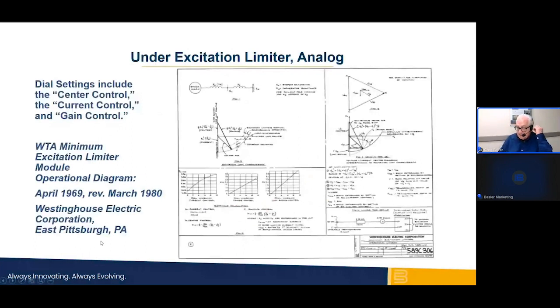The industry has relied on solid-state electronic analog control systems since they were invented. The underexcitation limiters and these analog controls are separate modules used to compensate the operation of the automatic voltage regulator. The concept essential for these UELs is that the underexcited pickup points are along a curved continuous locus in the underexcited portion of the PQ plane. To define the circle that traces the UEL arc, a center point is selected and a radius of that circle is selected. Experienced technicians and engineers develop techniques for finding the right settings for these parameters of the UEL. These techniques would be described as rule of thumb.